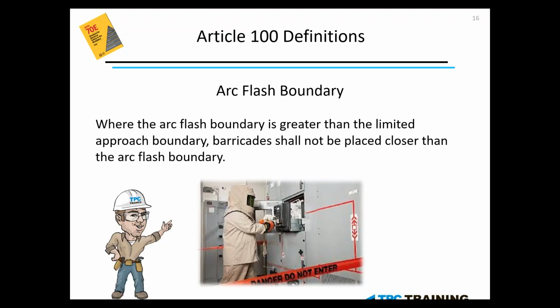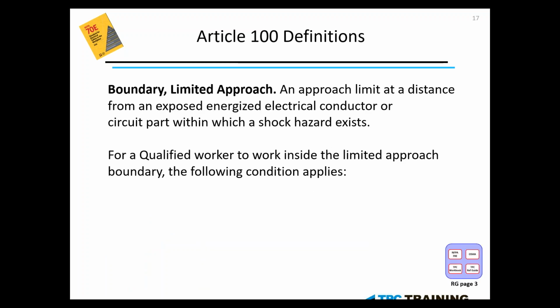Again, identifying with the fact that barricades shall be placed no closer than the arc flash boundary. This is the point at which we establish our barriers. Now, the first shock boundary I want to describe real quick here is called the limited approach boundary. It is an approach distance that is identified in our analysis where a shock hazard still exists. Within this boundary, only qualified persons may exist. To sum up, inside all of our barriers, inside of all of our boundaries, all 3 of them, only qualified persons may enter these boundaries.